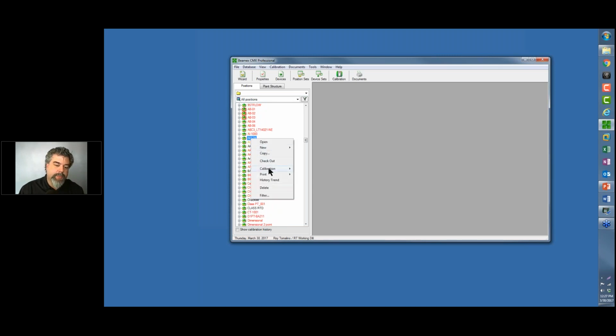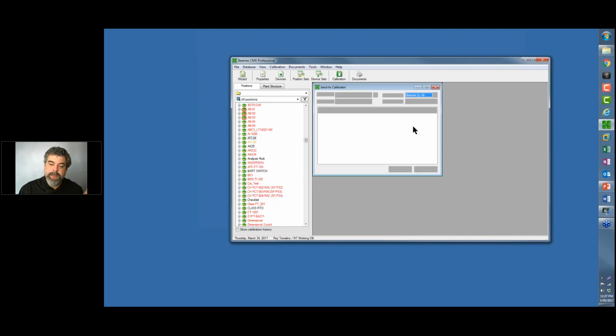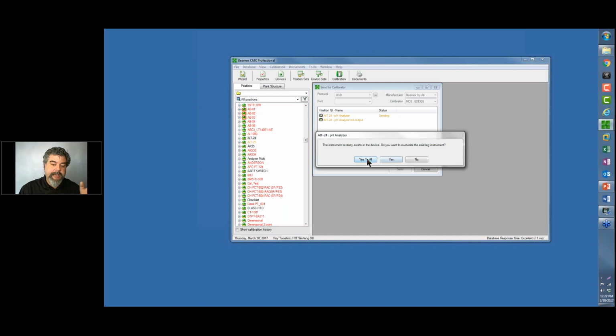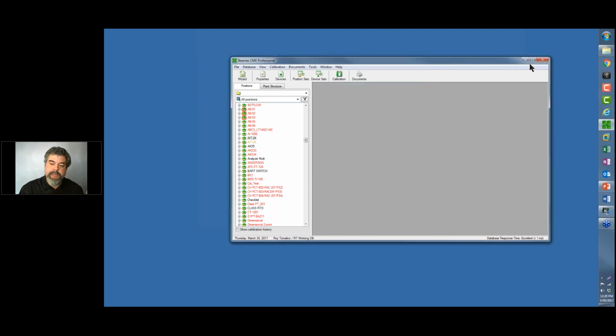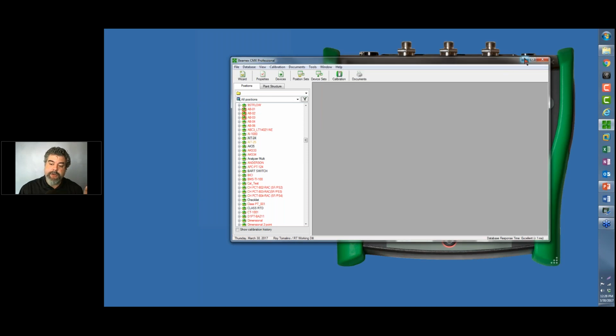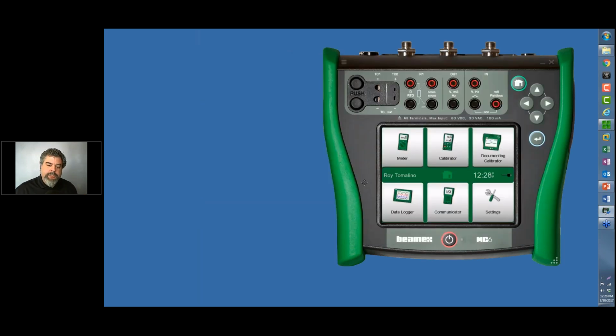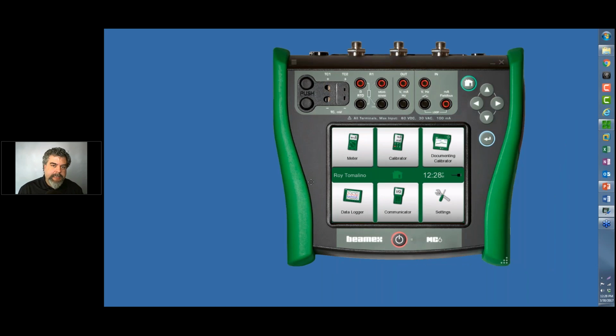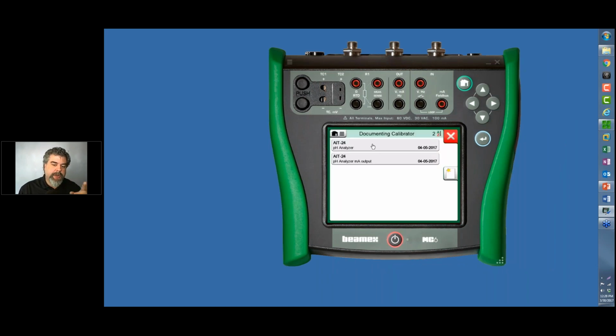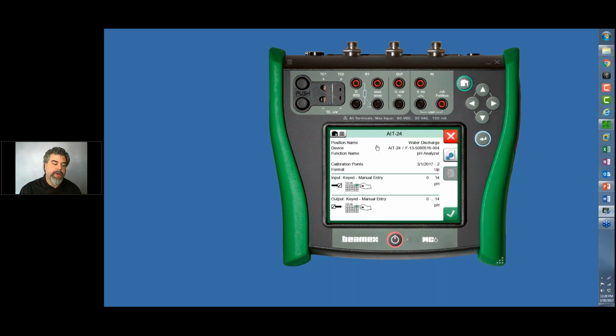Now I'll send this over to the calibrator, so I'm sending it now. There's my two functions, sending, and I already had them on there, but I'm going to overwrite them anyway, so that's done. Next thing I'll do is bring up my calibrator. So the calibrator itself, if I go to documenting calibrator, that's where our tests are. And the very top one, if you weren't using a transmitter and you were just calibrating a temperature probe, or not temperature, a pH probe rather, it would look like this.